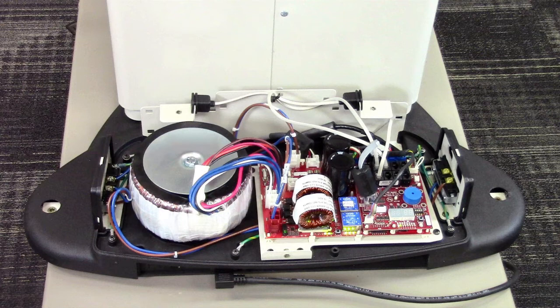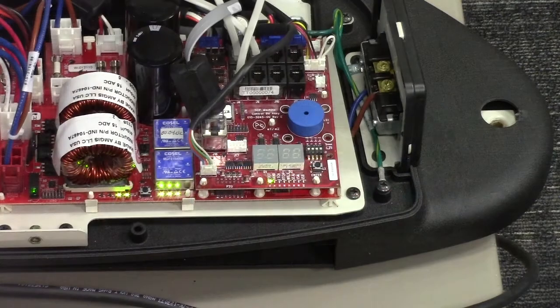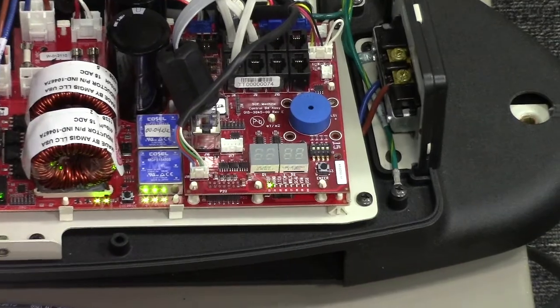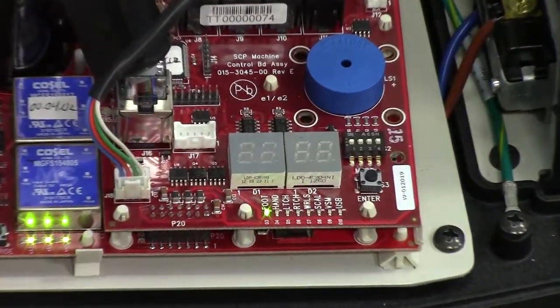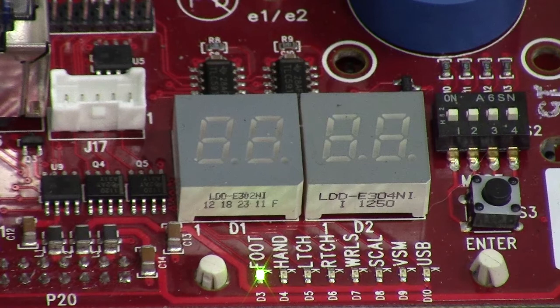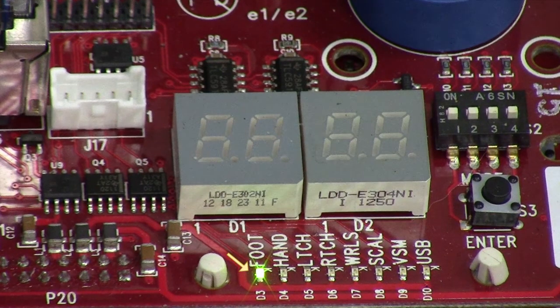The power supply PC board and machine control PC board are located in the base of the table. Fuses associated with incoming voltage, power to the motor control hub board, as well as the base actuator are located on the power supply board. All connections for the base actuator plug into the power supply board. The machine control board mounted to the power supply board receives commands from a controller and relays that command to the power supply board. LEDs indicate activity of the wired foot and hand controls, as well as wireless controls if equipped.